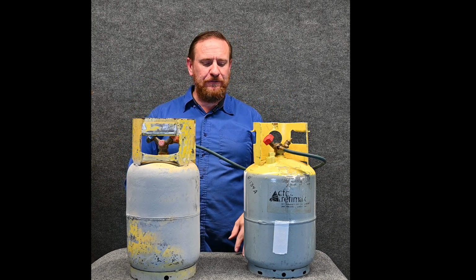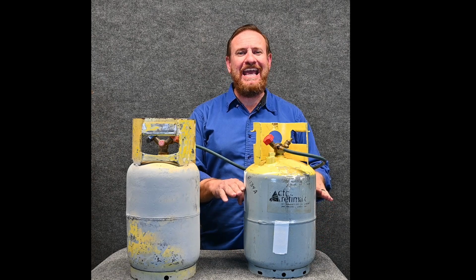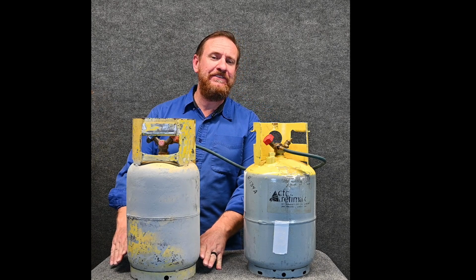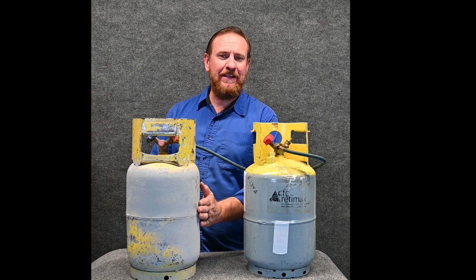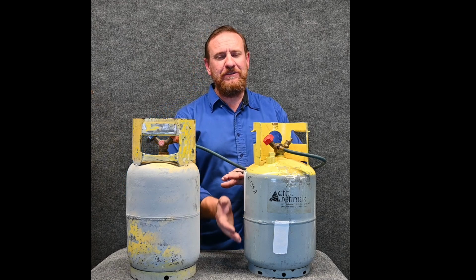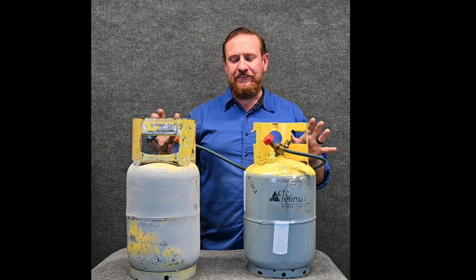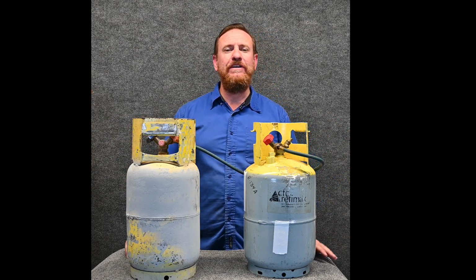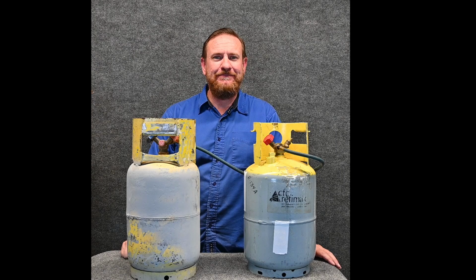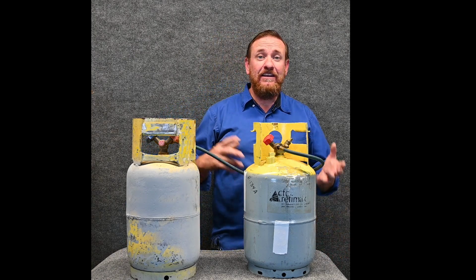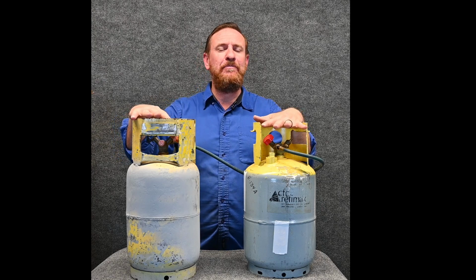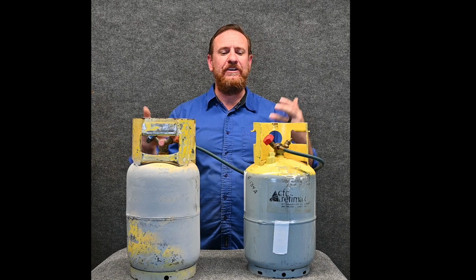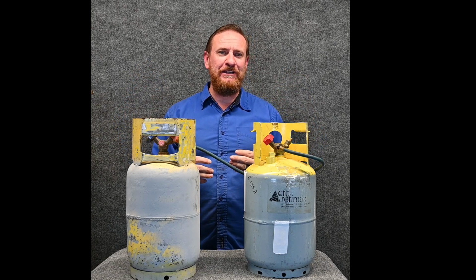Trivia question number 2. Let's say this one is filled at 80% capacity, the max we could ever fill it. And this one is only at, say, 10% capacity. But there's still liquid and vapor, only 10% liquid. And this one was 80% liquid, but they are still in the same room temperature. They're still at saturation. It's still 95 degrees in here. What do you think would happen? And the answer is, again, nothing, because there's the same exact pressure in both of these tanks. There's nothing to push the refrigerant from one way to the other. The tanks are equalized. The pressure would be equalized.